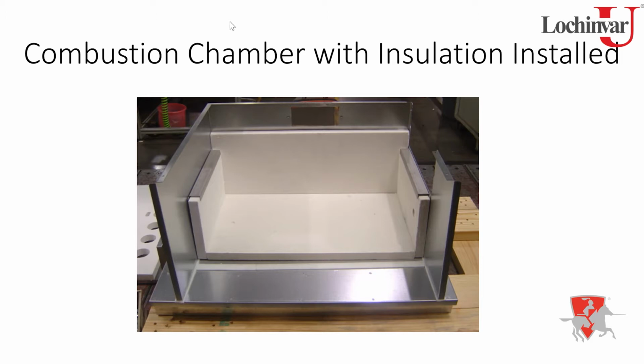Right. So yeah, just be careful about that. Using a pressure washer inside the cabinet is probably not a great idea, so I would avoid that. As you can see on the right-hand side in that insulation, you'll see a hole right in this area. That would be for your sight glass. There is a material there. It's not glass, but we call it that. It protects it and prevents the flue gases from coming out. That gives you your viewport into the combustion chamber.